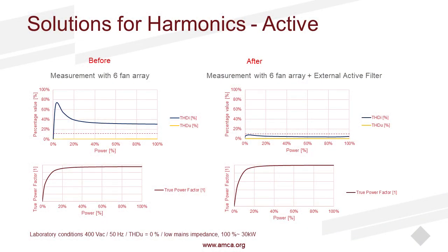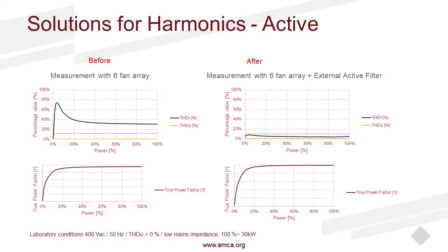So an example, laboratory conditions, again, we can see a before and after. So this is a 6-fan array and then a 6-fan array with the external active filter. On the left side, you can see that the THDI, total harmonic distortion current, is close to 35%, and then it starts to gradually decrease in percentage as the load increases. And you can see your power factor is not quite close to that 1. But then with the external active filter, we're able to reduce it significantly, and we're able to increase that power factor close to the 1 for a large portion of the power percentage.